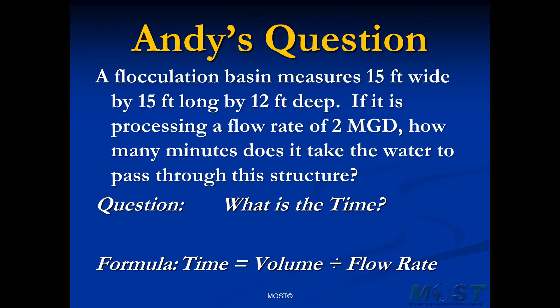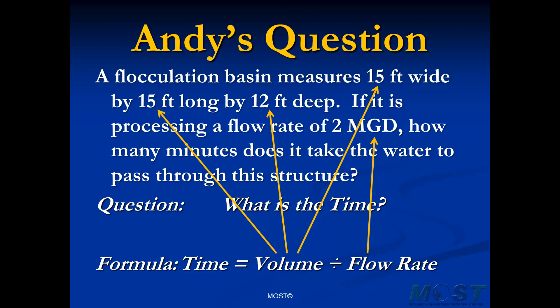So the fourth step is to look for the two variables: volume and flow rate. Do we have the volume in the problem? We don't, but we do have the dimensions of the basin, so with a little preliminary work we can find the volume. And the flow rate — we have a flow rate, but the problem is that it will be in the wrong units. We need our volume and flow rate to be in compatible units. If we want our answer in minutes, our flow rate should be in minutes-oriented units — gallons per minute. And if our flow rate is in gallons per minute, we'll want our volume not in cubic feet, but in gallons.